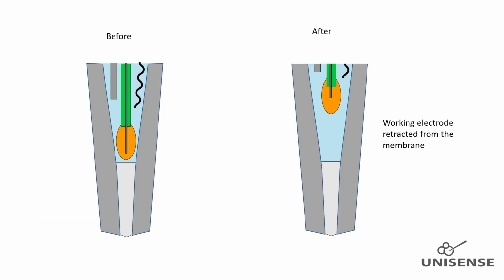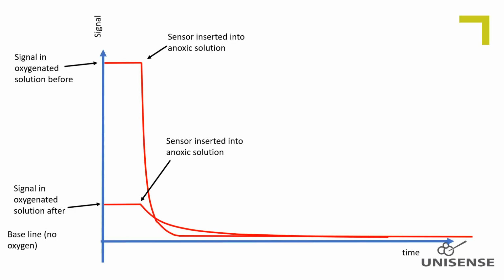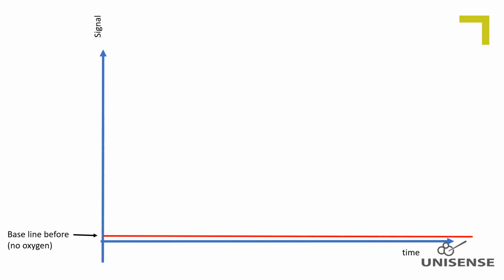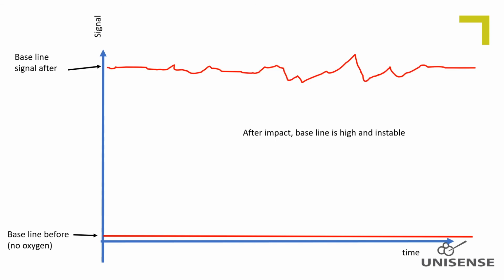If a sensor experiences a physical impact, like a drop on the table, the working electrode could be displaced. If the displacement results in a working electrode retraction from the silicone membrane, the signal will be slow and sensitivity low. The sensor will still work, but has lost its original performance. It is unfortunately not possible to restore original performance. A physical impact, like a drop, could also damage the glass insulation of the platinum wire which connects to the working electrode. This will typically result in an elevated and noisy baseline signal due to exposure of polarized platinum surface to the electrolyte. Chemical reactions taking place on the exposed platinum surface will create a current which will overlay the working electrode generated current. The size of the baseline increase will depend on the degree of damage to the platinum wire insulation. Such damages cannot be repaired.